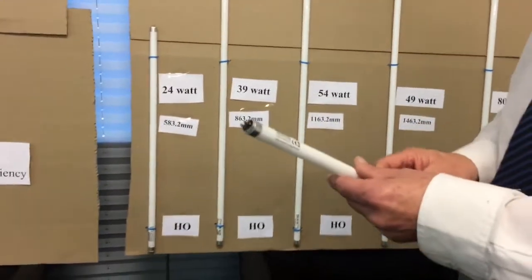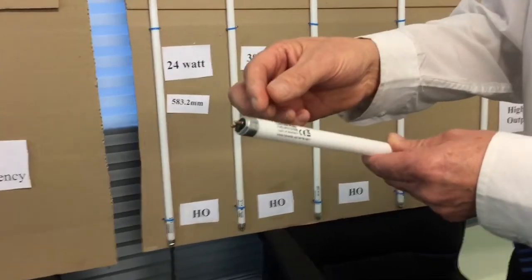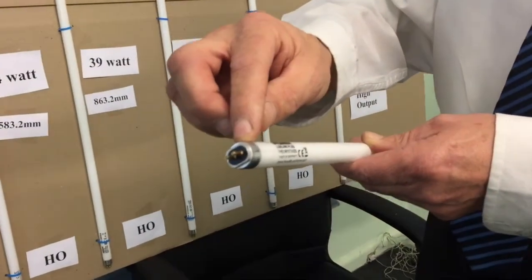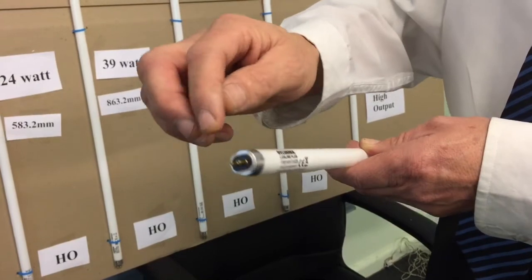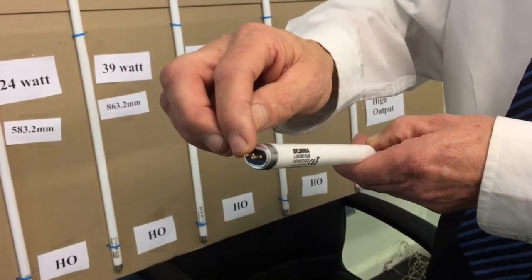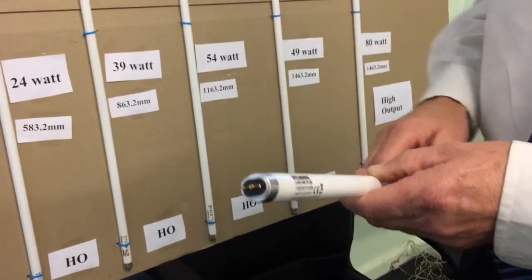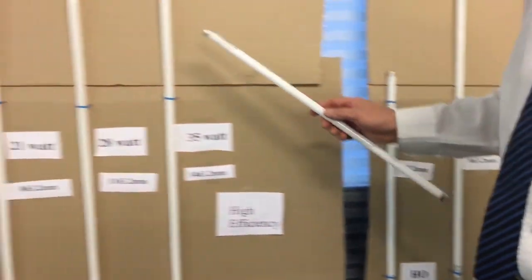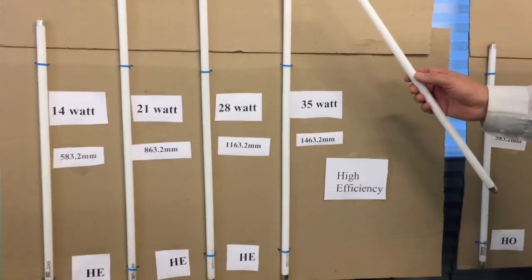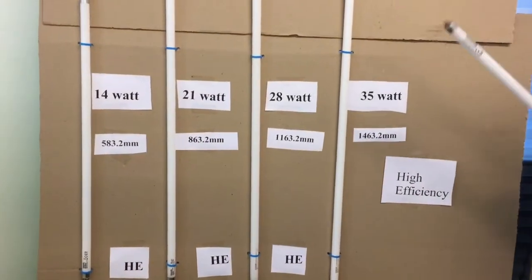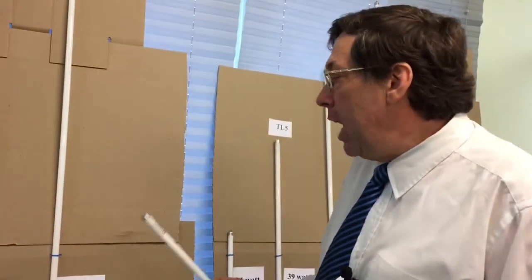The diameter of the T5 will be 16 millimeters in diameter and the base type is a G5. Both units run off high frequency ballasts. They are environmentally friendly with low mercury content and the rated average life is 24,000 hours.